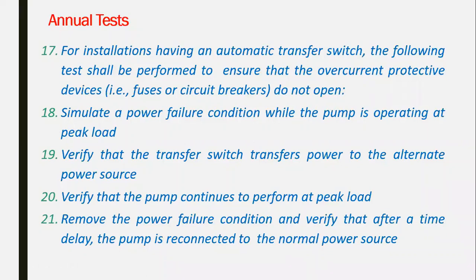To assure that the ATS, or the transfer switch, is working, we have to simulate a power failure condition, like simulating the electricity is gone from the transformer side while the pump is operating at a peak load. So run the pump at the peak load and simulate the power failure, and check the performance of the ATS, whether it automatically transfers the electricity to the generator, verifying that the power switch transfers the power to the alternate power source and that the pump continues to perform at the peak load. Even during the transfer, the pump is working at peak load.